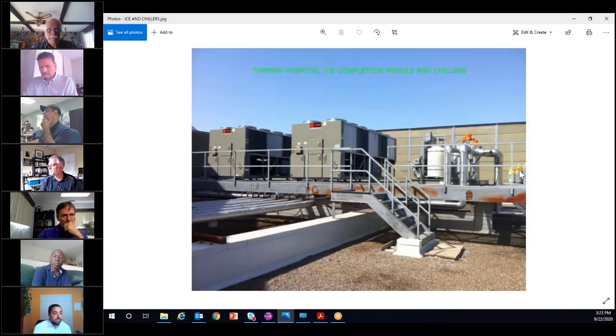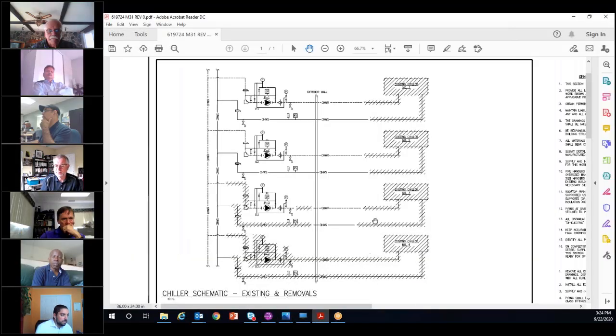The original picture here shows where the chillers were originally. This structural platform still actually remained. There were 4 chillers here before. 1 where this kind of pump station is here, 2 where the new chillers were, and then there was an empty bay off to the left here where the picture doesn't show. So there were 4 originally, and then after the project was done, there were 2 of similar size, plus this pump station, plus the 8 ice tanks off the roof, mounted on an on-grade slab. So if I can quickly show here.